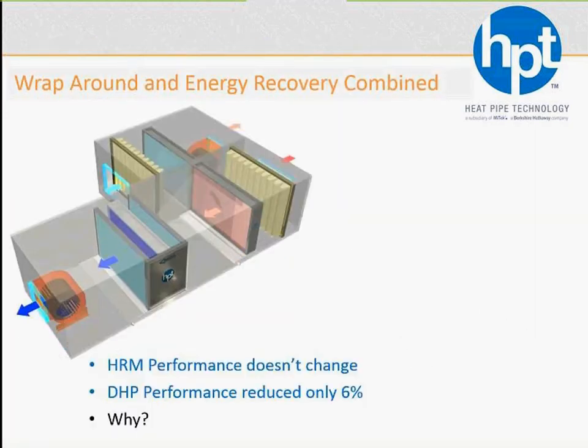Moving on. What happens if you combine energy recovery with wraparound heat pipes? A lot of good things happen, I say, and we'll show that to you in a minute. This is, let's say, a typical air handler. Air comes in, you capture some BTUs from the exhaust, pre-cool the air coming in, and then you feed that to a pre-cool heat pipe, cooling coil, and reheat heat pipe. Actually, surprisingly, the DHP performance doesn't take a huge hit in this particular example. Of course, one has to do the numbers for their geography and location, and our Slick Plus can help you with that. If you run into some difficulties, our engineers will be more than happy to help you make that decision. Of course, the premise here is you're looking for wraparound heat pipes to pre-cool and reheat, okay? And that's why you're including a wraparound heat pipe.